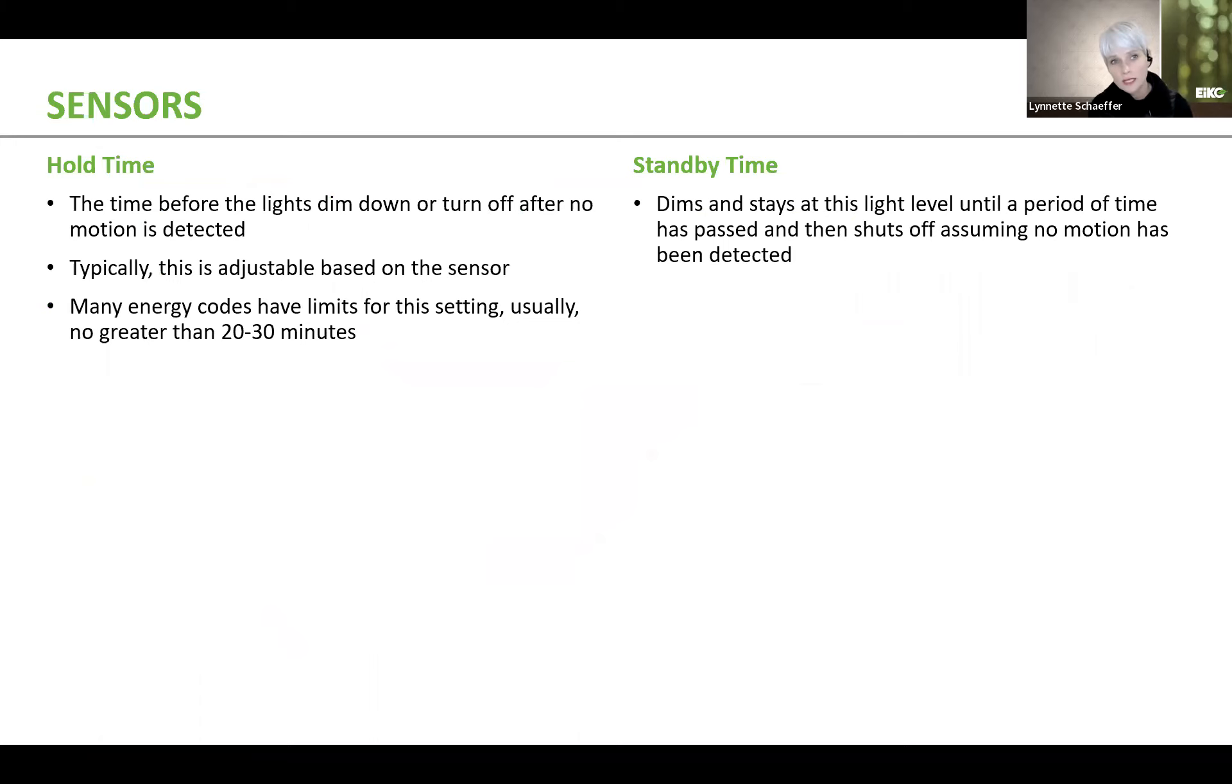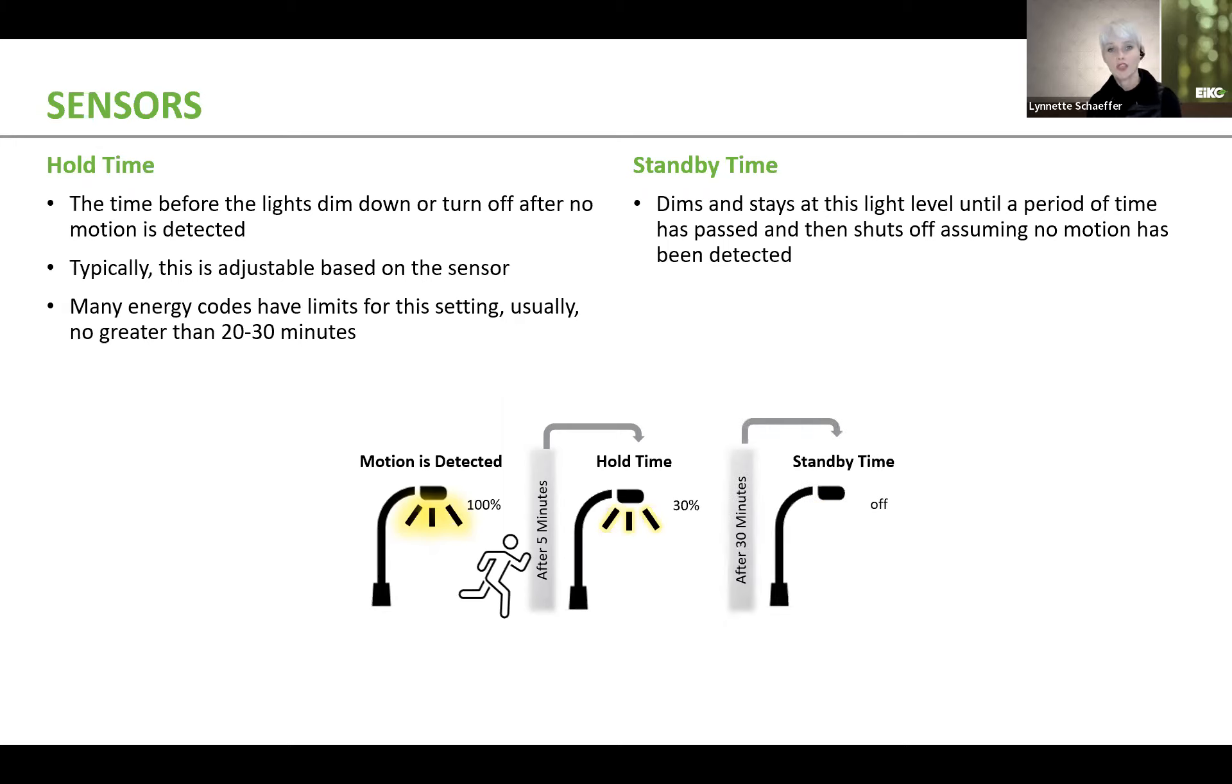Now, many sensors have a hold time, a standby time, and you also have the ability to set the sensitivity. So first of all, let's talk about hold time and standby time. So in this first animation, you are going to see the fixtures off, but when motion is detected, it goes to 100%. Of course, that can be programmed to be less than 100% if you want to, which I'll talk about here in a few minutes. Then after five minutes with no motion, that is what we refer to as the hold time. And then after that, you're going to notice that after five minutes of hold time and there's no motion, then the lights will go down to, in this example, 30% light output.